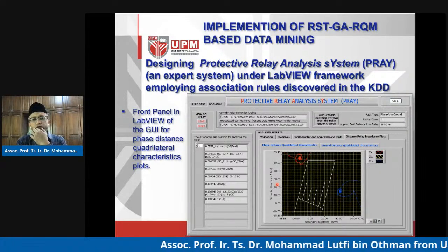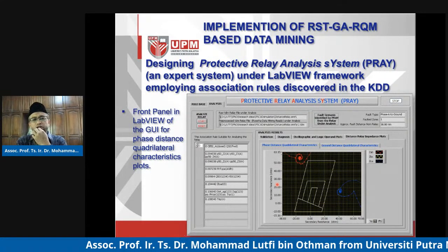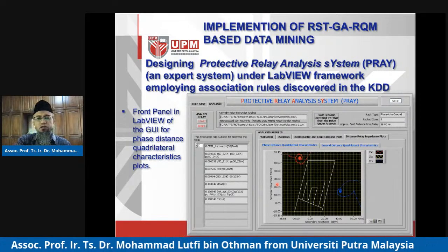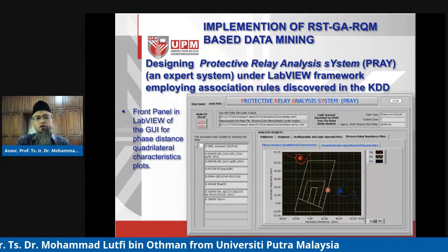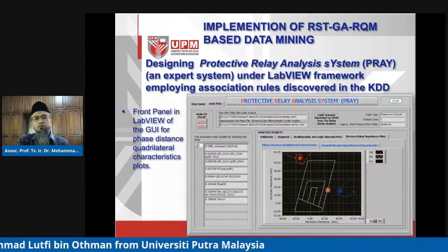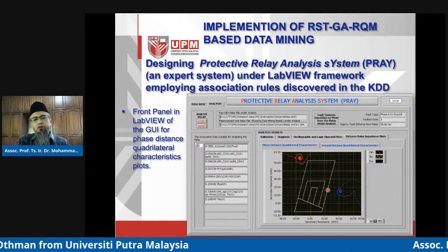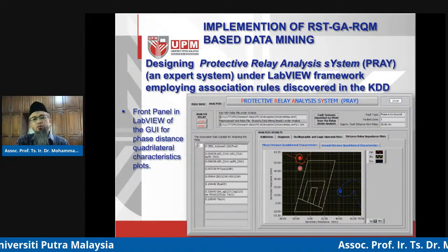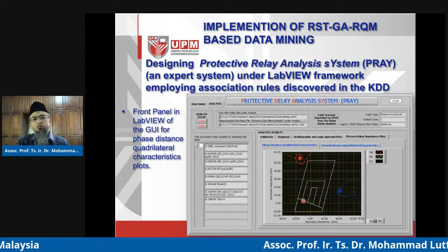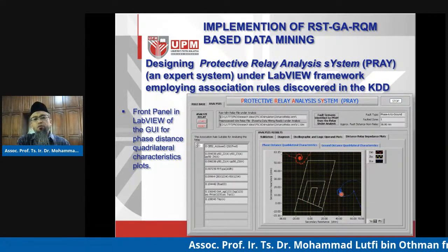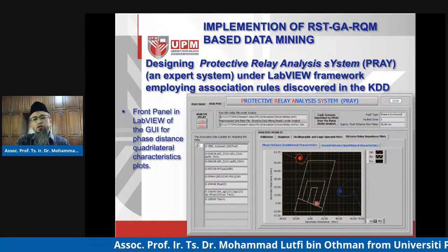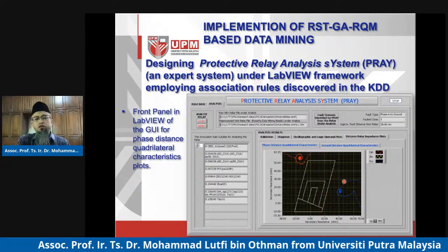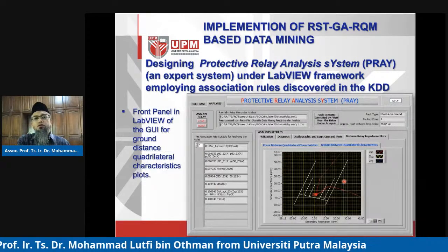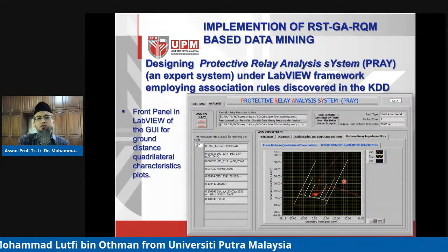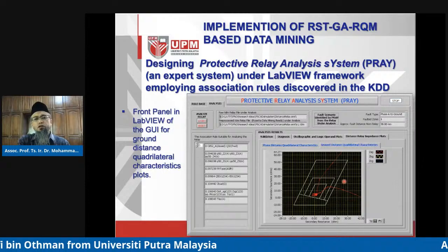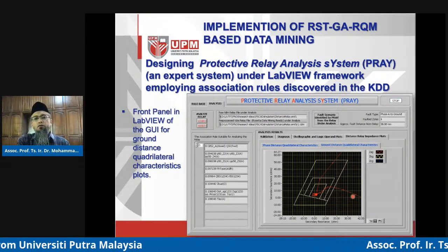If you were to plot the operation characteristic and see how the trajectory of the impedance behaves, we're talking about a phase A to ground fault. Of course, for phase to phase, you wouldn't see the trajectory intruding the zone, so we need to look at the phase to ground fault operation characteristics. It's rightly so, as we expected, for one of the phases.